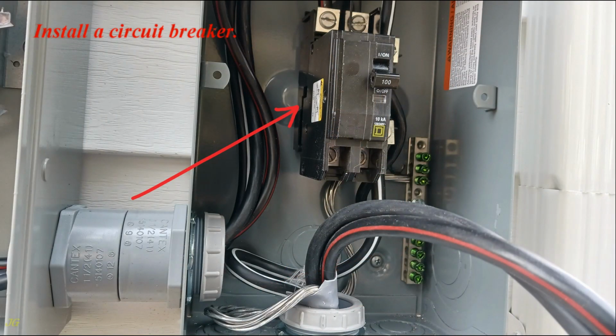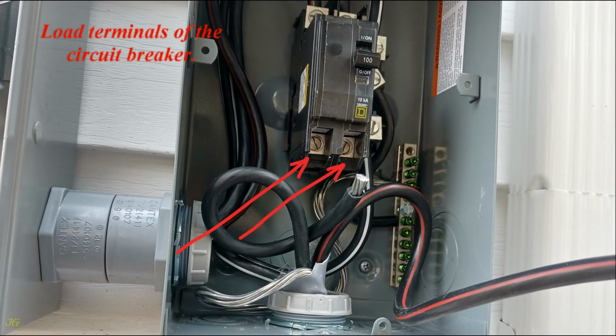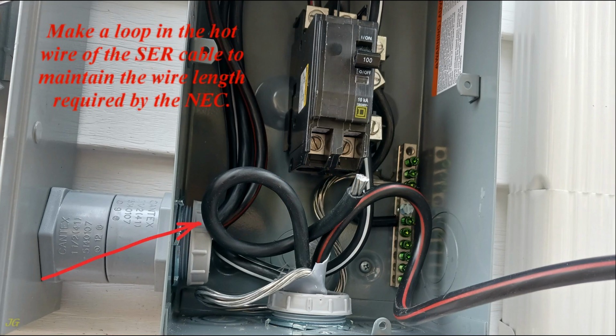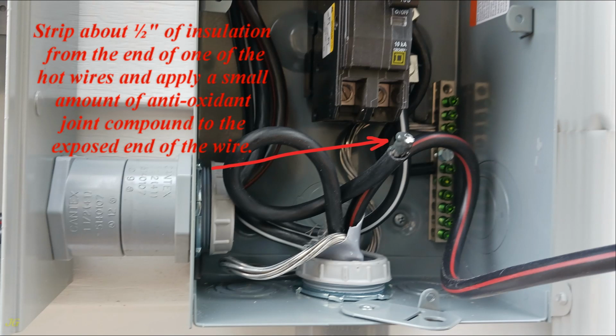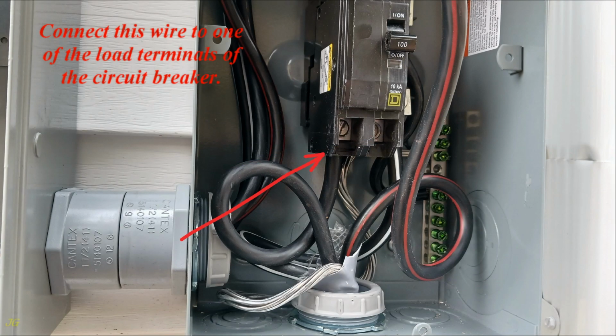Install a circuit breaker. Load terminals of the circuit breaker. Make a loop in the hot wire of the SER cable to maintain the wire length required by the NEC. Strip about 1/2 inch of insulation from the end of one of the hot wires and apply a small amount of antioxidant joint compound to the exposed end of the wire. Connect this wire to one of the load terminals of the circuit breaker.